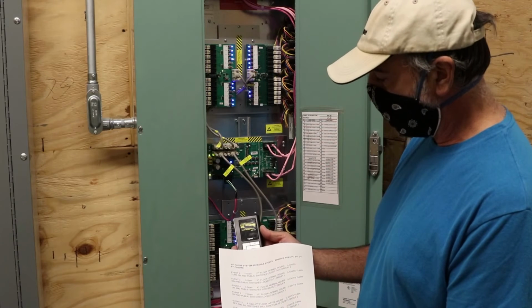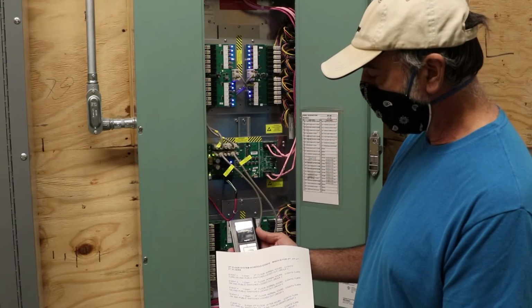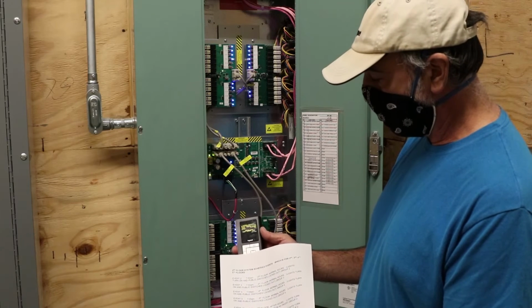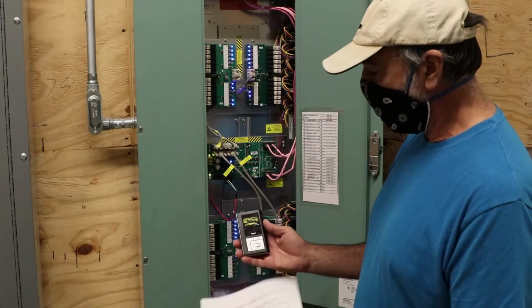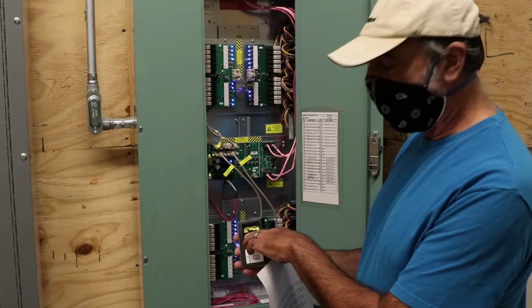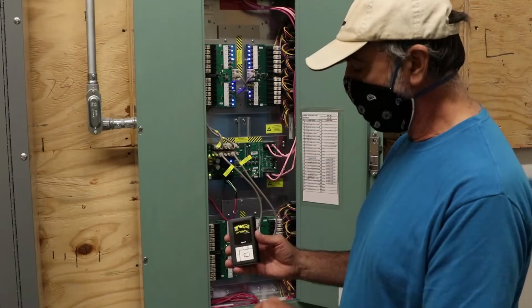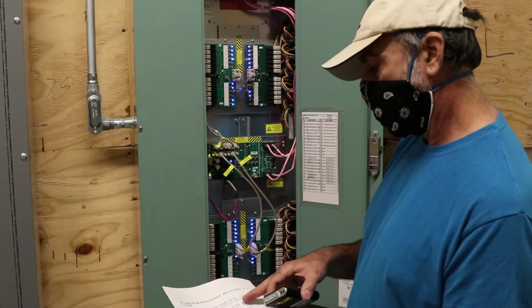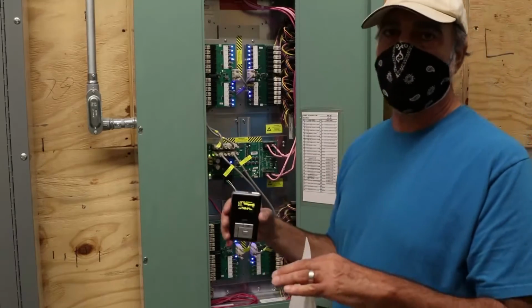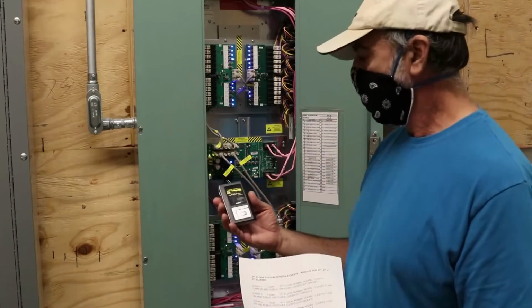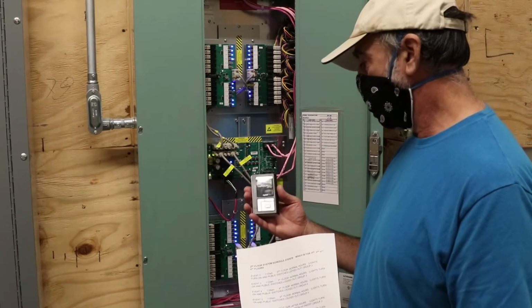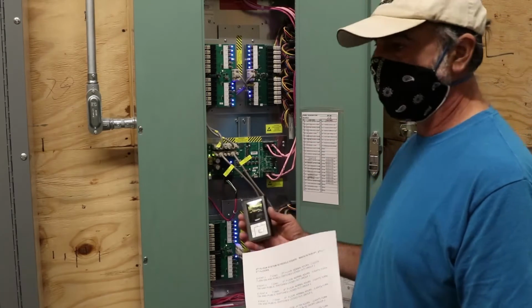Event 2 is normal hours at 7:02, and it doesn't say floor 2 because it just doesn't have that term, but group 2, which also was on here, represents a group of lights. In our case, it's all floor 2.